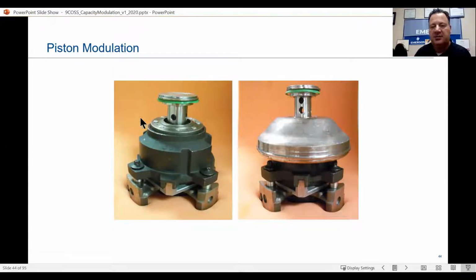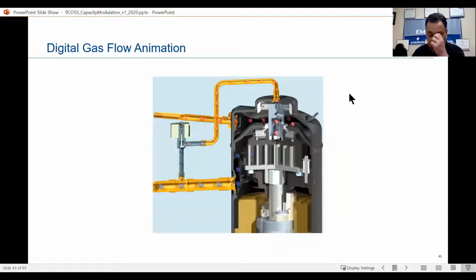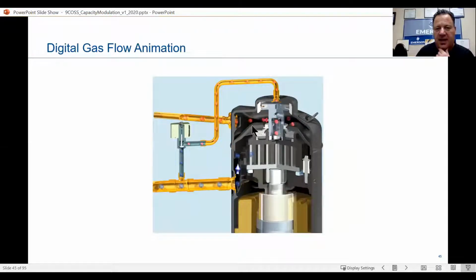All right, and it's running right now. These three holes here are bleeding off just enough gas to push off the top of the compressor and push it down. All right. And I'll show you what happens. Now they've added the muffler plate over here, and you can see the holes inside that plunger, that piston, if you will, that's blowing the gas out, coming through that discharge line in the dead center of that scroll set. Now, what happens here is you can see this, and for capacity, you can see we've got little lightning bolts coming out there to indicate that we have power to it. This is normally closed. All right, now it's running full capacity.